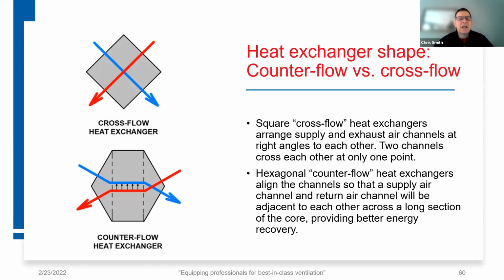And so that one point would be the chance that those two air channels have to exchange energy with each other. In a counterflow heat exchanger, this hexagonal shape, the air streams are organized in such a way that they actually go at each other like playing chicken over the distance of the middle of the heat exchanger. So as the air streams take time to pass through that distance, they have more opportunity to exchange energy along the distance of that core. So you get higher opportunity for energy recovery, and you get distinctly higher performance out of this shape. So look for a hexagonal or counterflow heat exchanger.